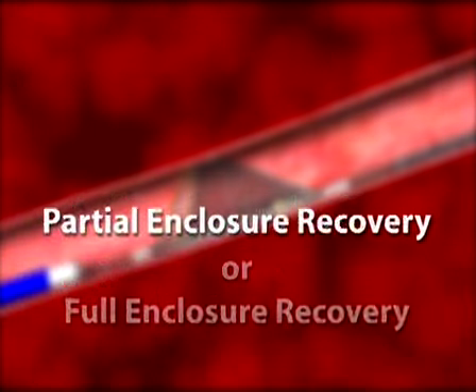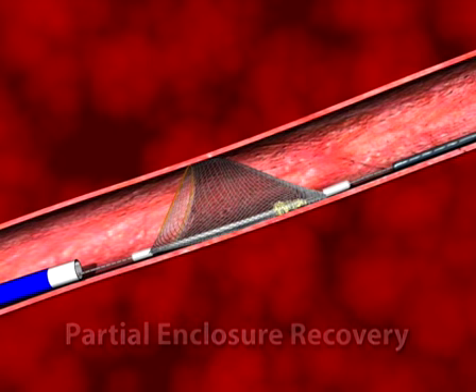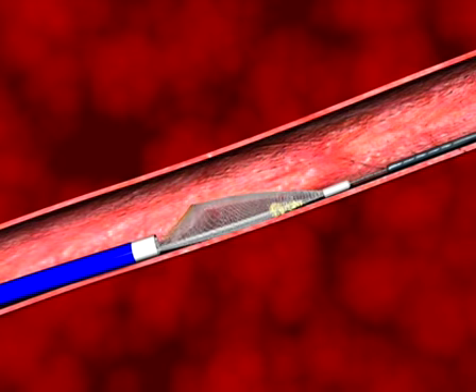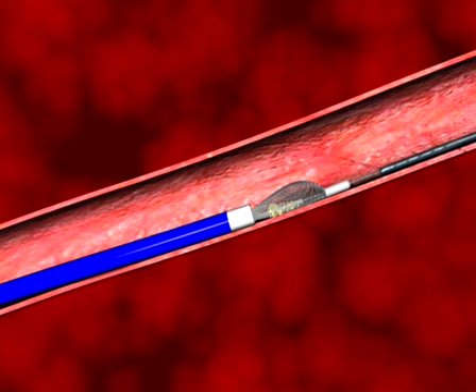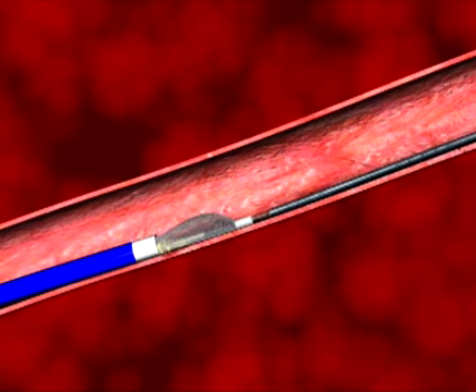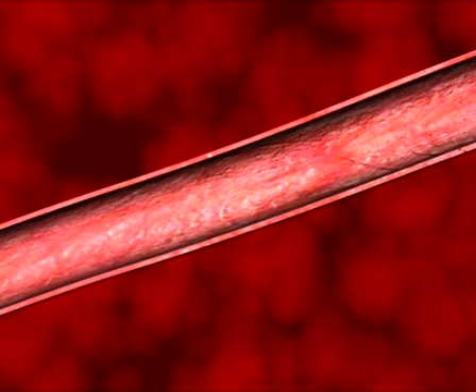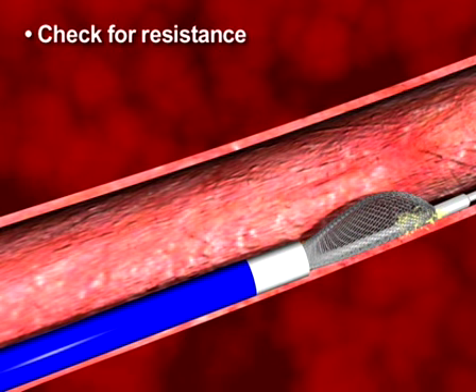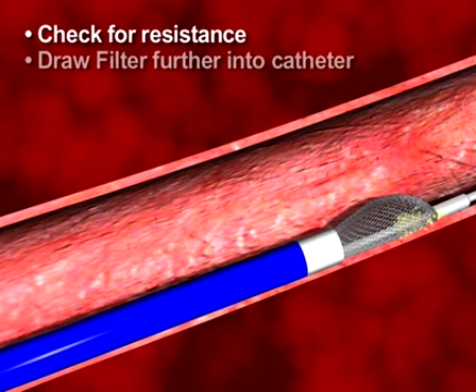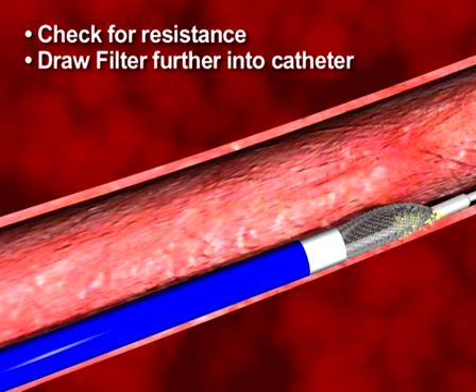For partial enclosure recovery, gently advance the catheter over the filter until the filter gold marker is within the catheter, closing off the mouth of the filter but leaving the distal portion of the filter outside the catheter. Withdraw the catheter and capture wire as a unit, being careful to not interfere with the site of intervention, and remove from the patient. If resistance is felt, advance the filter and recovery end of the catheter distally, and draw the filter more fully into the catheter before attempting to withdraw.